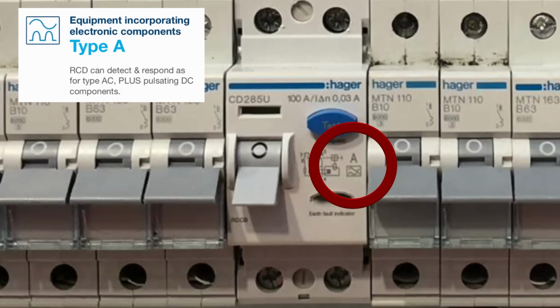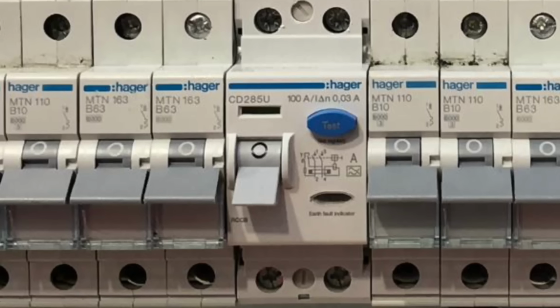Fantastic. So if this wasn't an A type, there's a potential that this could be almost stunned by the DC leakage current going back into it. That's exactly correct. And then it wouldn't trip under earth fault conditions. So now by putting in an A type RCD, we're overcoming that problem. Yes, we are. Just absolutely brilliant. I love this kind of forward thinking that Hager are demonstrating here. Absolutely brilliant. There's one other further point actually.